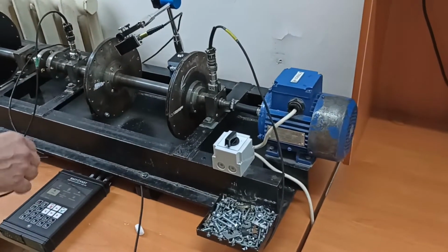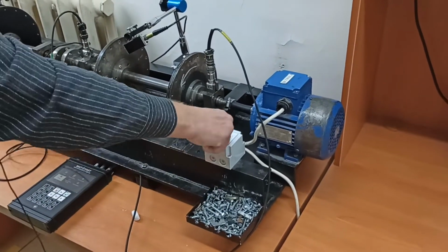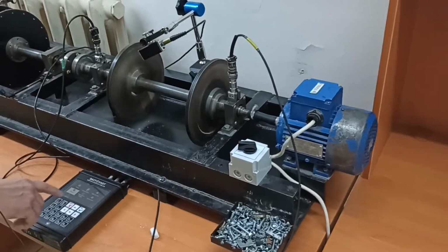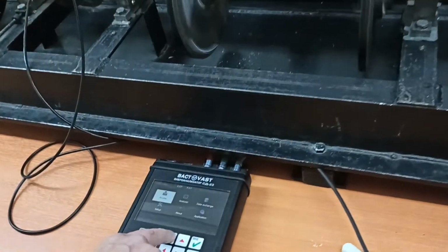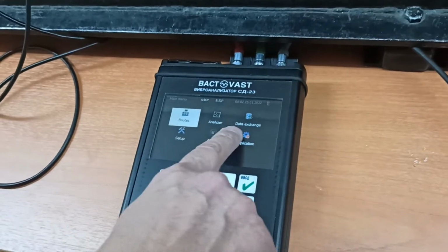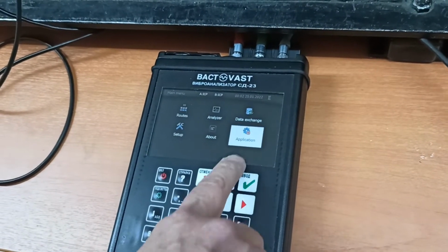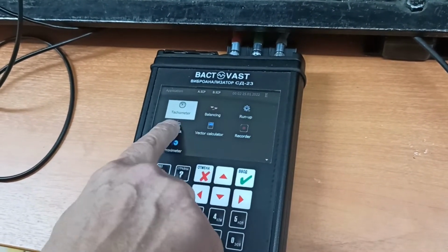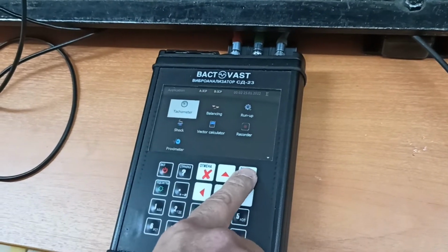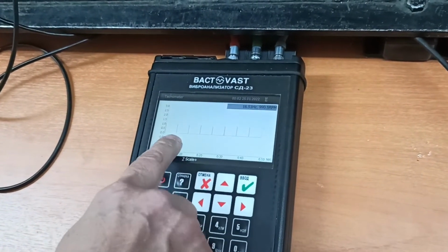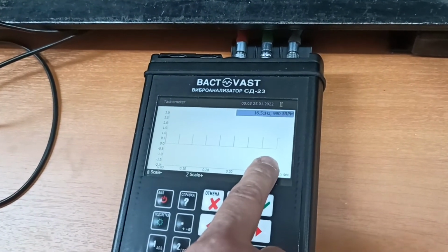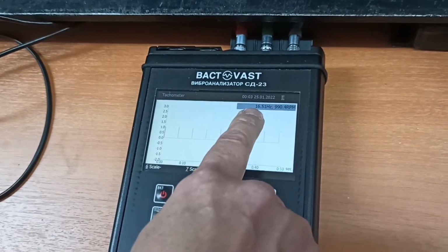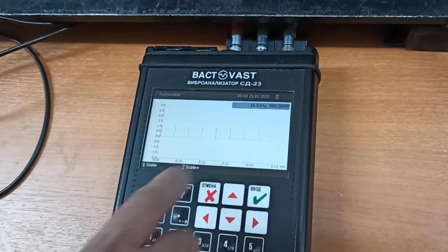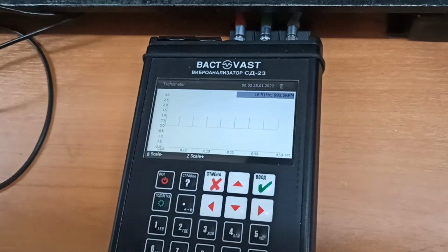Before you do any job, you check the tacho probe. We start our machine, and in the vibration analyzer we go to the applications, and here we have a tachometer function. So here it presents the signal from the tachometer, this is the rotation speed that we get.